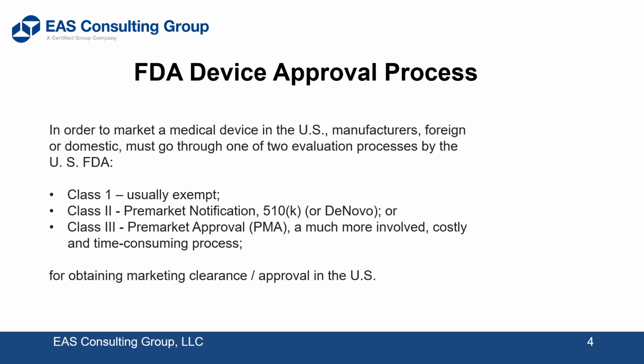When you get into moderately risky devices that can have a downside, can cause injury or death, generally more injury, you're looking at class 2 type devices. In Europe, there's class 2A, 2B, but US class 2. And here, generally, that is handled by the 510K process. We'll mention the de novo in passing, but it's basically the 510K.